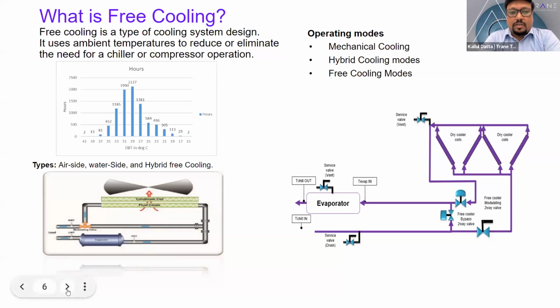Before getting into the waterside economizer, let me just touch base on the airside economizer system. An airside economizer is typically used for a packaged rooftop or tied to indoor air handling systems, allowing filtered outside air into the space when the outdoor temperature drops below the indoor room temperature, thus eliminating the need for the refrigeration cycle to be running. The indoor space is being cooled, yet the refrigeration system is not running. Hence, the name free cooling. Now, if we transition back to the chiller world, the equivalent would be a way to supply whatever chilled water temperature we need without running the chiller. That is called a waterside economizer. In terms of chillers, it is called free cooling.